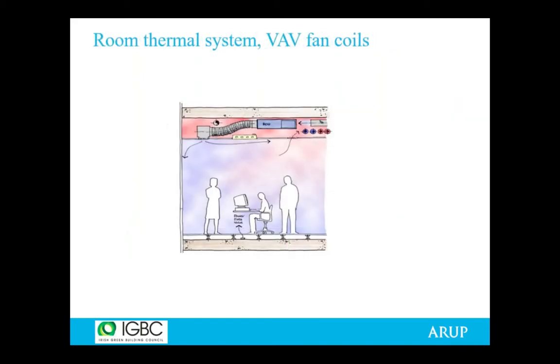Variable air fan coils are another one that should be considered. Just a fast snippet: the fan coils can have a DC fan. You can reduce not only the water flow that comes into the coils, but also the air coming from the fan coil. So if there's no load, the speed of the fans decreases, and they supply less air because there's no thermal load. In that sense, by reducing the fan speed, they reduce the fan energy, and they are a means to achieve low energy ratings as well. These systems should definitely be considered, which is already common in offices.